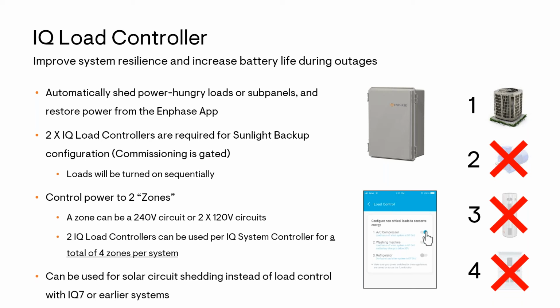Another interesting note about this device is that it can also be used for solar circuit shedding. So with earlier generations like the IQ7 or IQ6, there's a ratio of a maximum of 1.5 to 1 solar AC power to battery AC power. That's in order to allow the batteries to be large enough to absorb all the power from the PV system and avoid that microgrid getting overloaded. So in some situations, say you're retrofitting a system with a very large PV system and you're adding batteries, you might want to disconnect some of that PV based on the size of the battery so that you have a stable microgrid. So again, the IQ load controller can be used for shedding that portion of the PV, or disconnecting that portion of the PV.